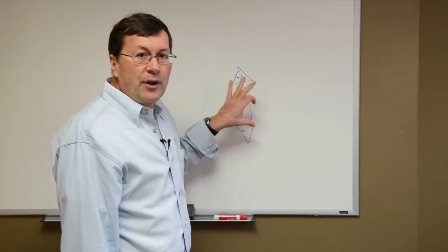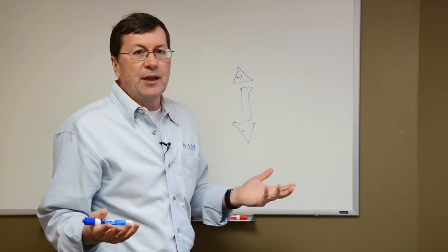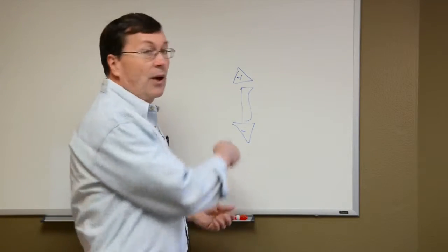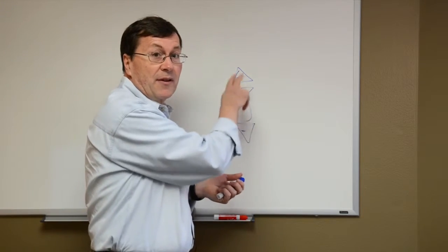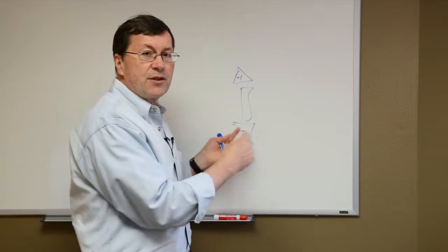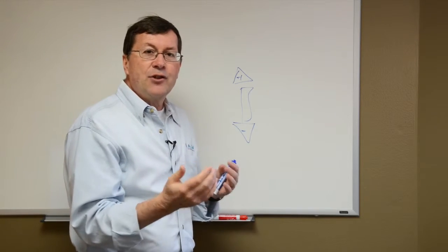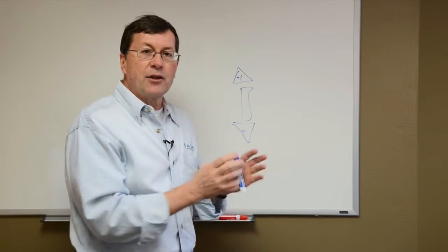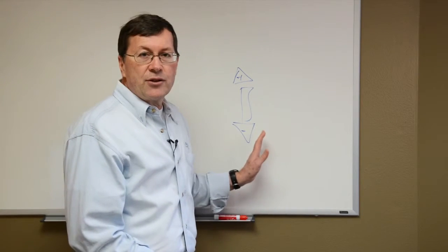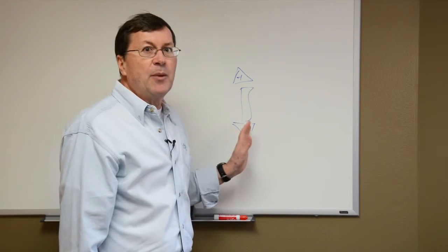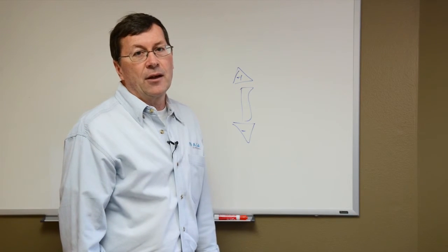So the idea that you need to be able to change a GUI in response to a user concern, you have to be able to do that. That's critical. Now this is an easy change because it's still a plus and minus with the thing in the middle. But let's say it went from this to a scroll bar, or from this to a dial. That kind of change, you don't want that to impact the core functionality, which is in the device. So GUI changes should be able to be implemented independently of the core functionality, and that's why we like the divide and conquer architecture.